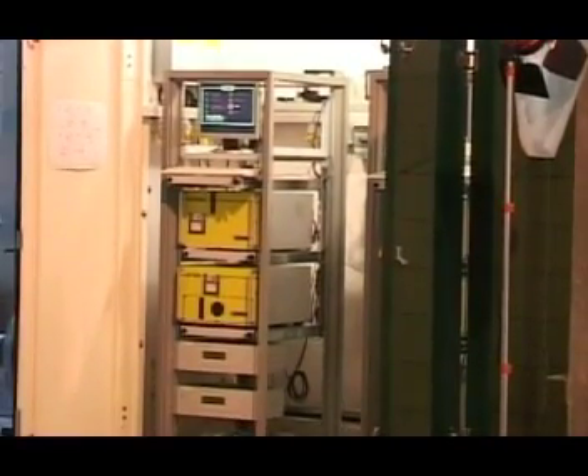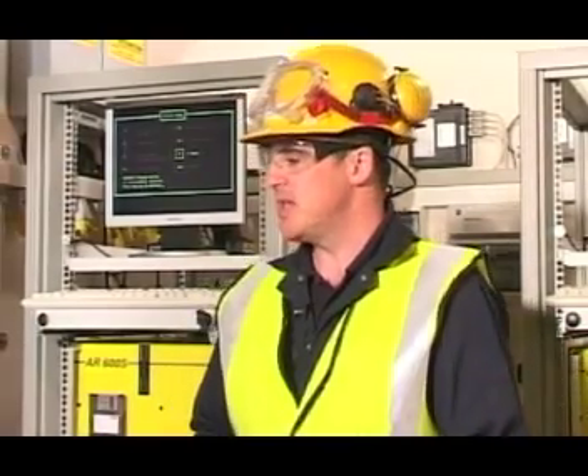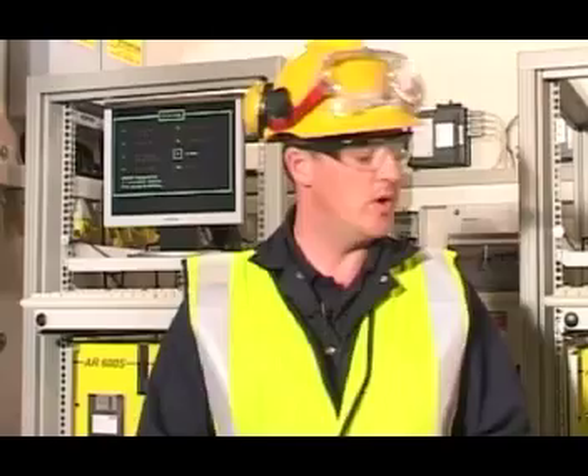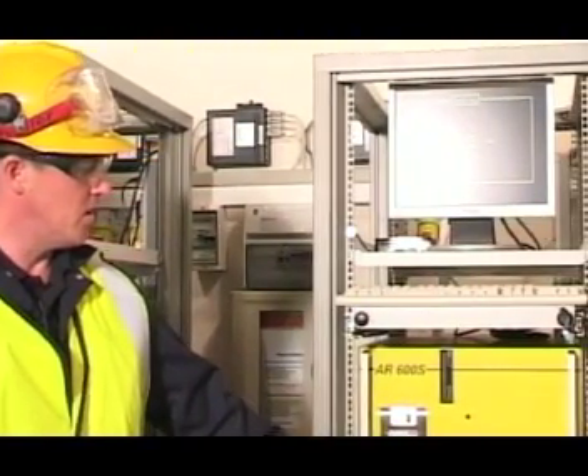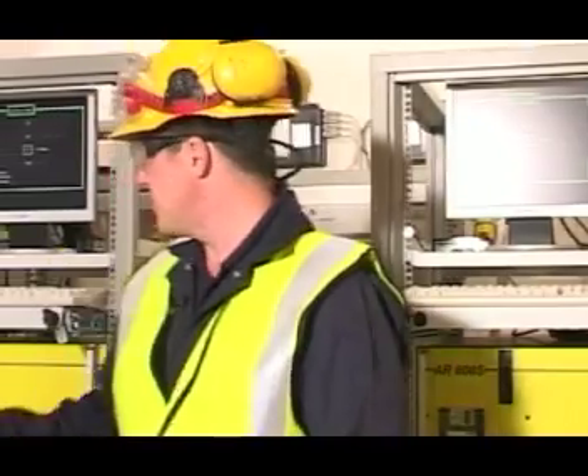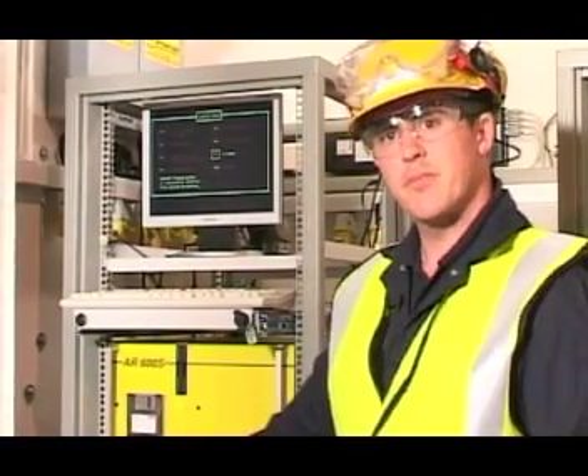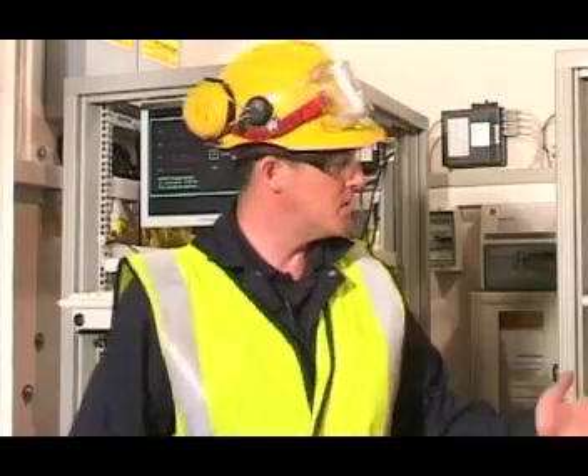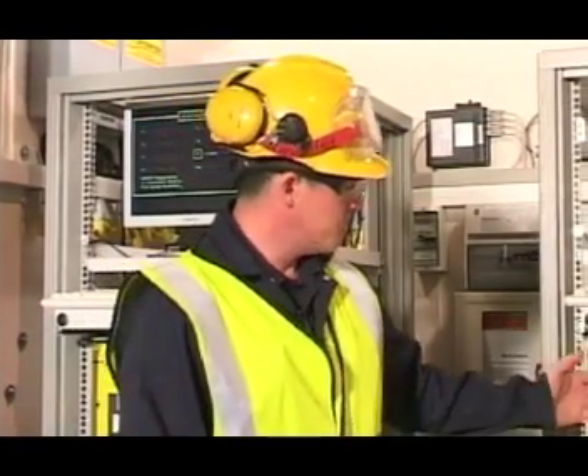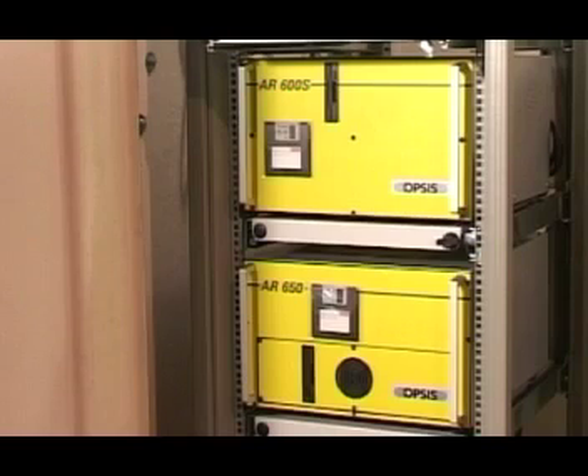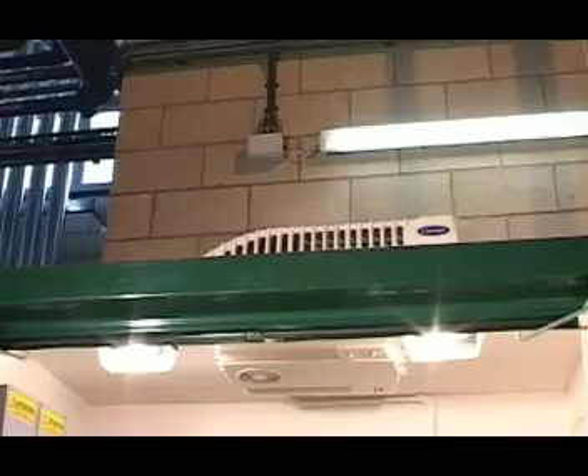The client decided that he wanted to keep the 2 systems completely separate in terms of reliability and data backup. So here we have a system that covers our stack emission system 1, and then we have another system here which does stack 2. Both cabinets are identical to each other. We have an Opsis AR600 analyzer measuring NO, SO2 and NO2, and then we have an AR650 measuring CO, HCl and water. Both systems will be calibrated identically and measure the gases identically.